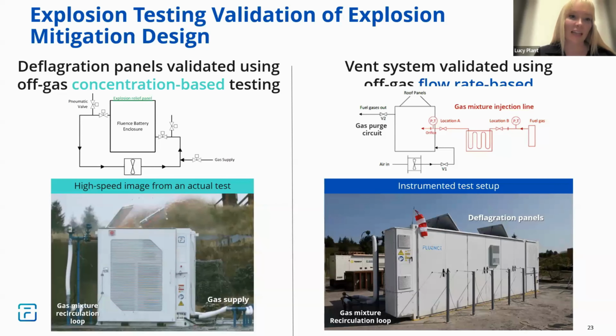This is our deflagration panel testing. So this is what we do in an explosion facility in Newcastle in the UK. We actually measure, first of all, the gases that come off when those cells go into thermal runaway. We then use that information to do the testing. So we'll actually use the gas itself that you will see from those cells. We will pump that into a dummy enclosure, see that pressure build up, and we want to see those deflagration panels pop up off the top.